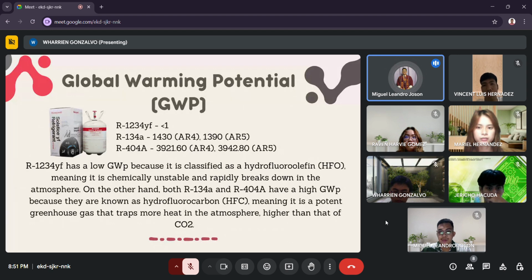R-1234yf has a low GWP because it is classified as a hydrofluoroolefin or HFO, meaning it is chemically unstable and rapidly breaks down in the atmosphere. On the other hand, both R-134a and R-404A have a high GWP because they are known as hydrofluorocarbons or HFCs, meaning they are potent greenhouse gases that trap more heat in the atmosphere than CO2.